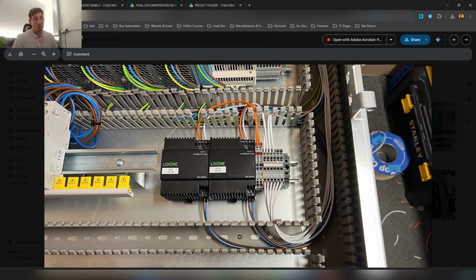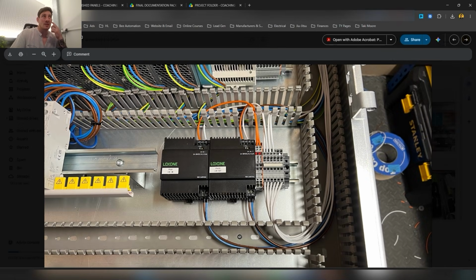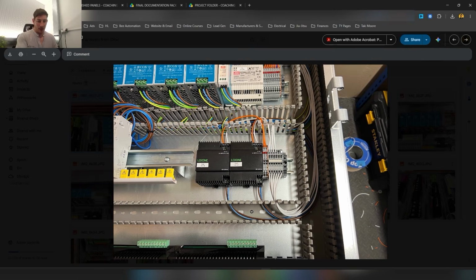What we could also do, and it's recommended, is to actually earth this. I'm not sure if I do that later on, I'm not doing it here, but it's one of those things I would do at the end. You could connect all the 0 volts to earth as well, just so they're all at the same potential. The only time you might not want to do that is on an industrial site that has what's known as a dirty earth, with a lot of noise and interference, and if you've got sensitive analog or extra low voltage signals, you could get false readings and interference. But this is going into a residential property, so that's absolutely fine in this case, and would actually be good practice.